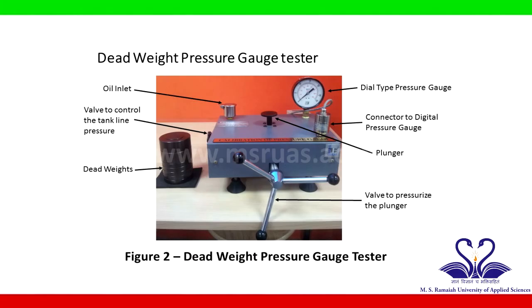It comprises of a dial type pressure gauge, a connector to digital pressure gauge which is optional, a plunger, a valve to pressurize the plunger, a set of 7 dead weights, a valve to control the tank line pressure, and an inlet to fill the tank of the equipment with oil.